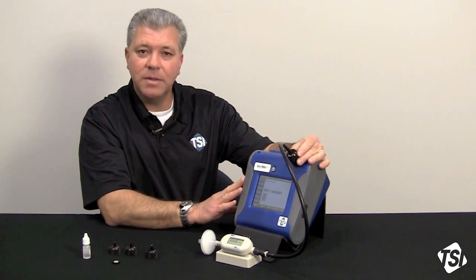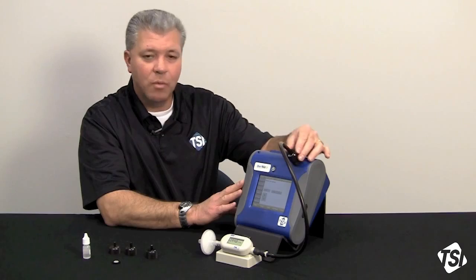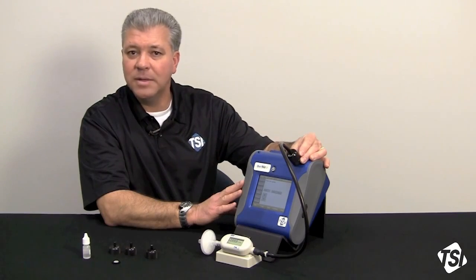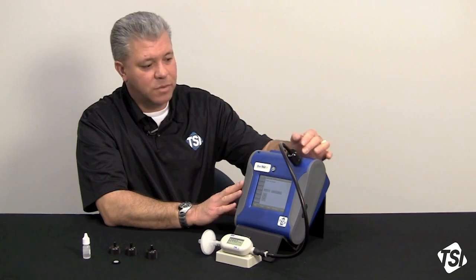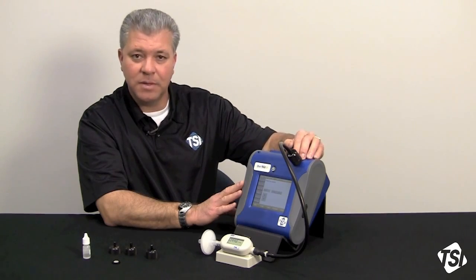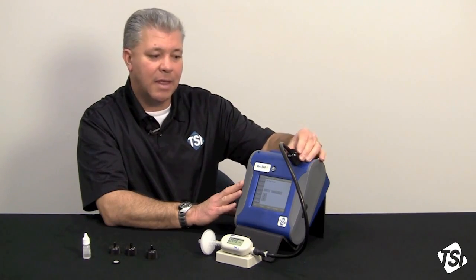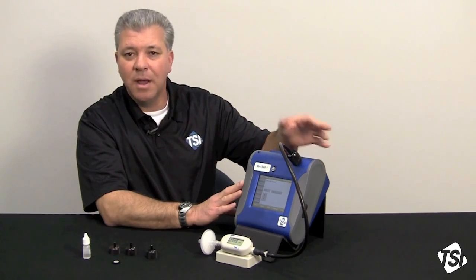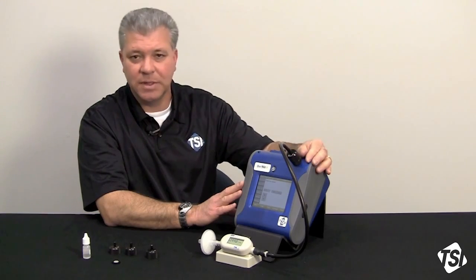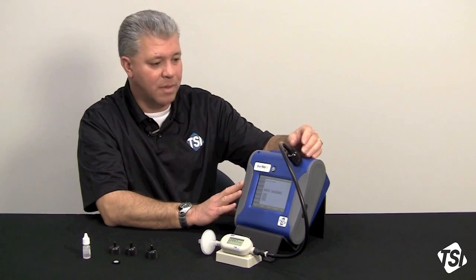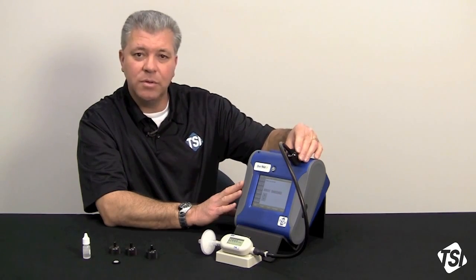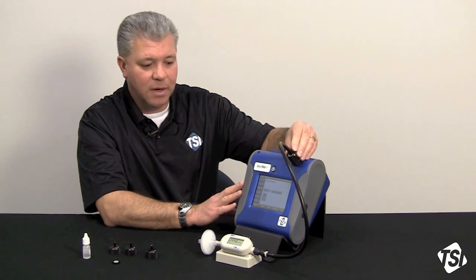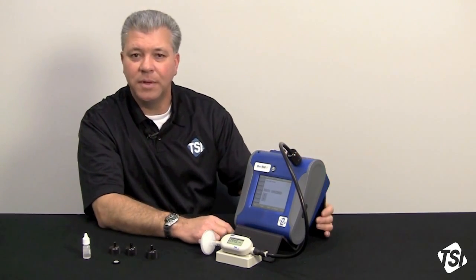It is recommended to do your flow calibration with your impactor in line, as it does create a slight back pressure. So if you just went and flow calibrated this without anything on the inlet and then put an impactor on, you could be off by about 50 or 60 cc's roughly, somewhere in that area. So I just want everybody to take note, always use your impactor, your inlet conditioner, when you're doing a flow cal with the DustTrak 2.